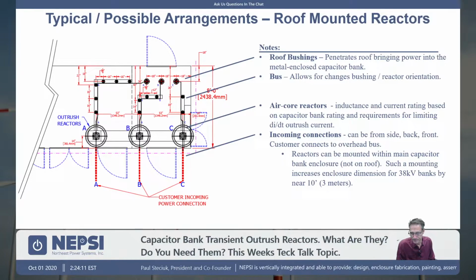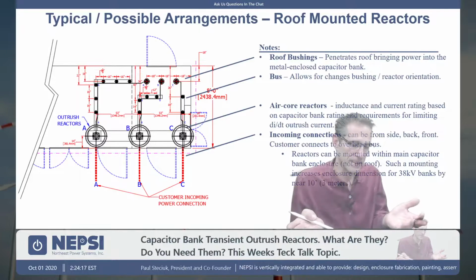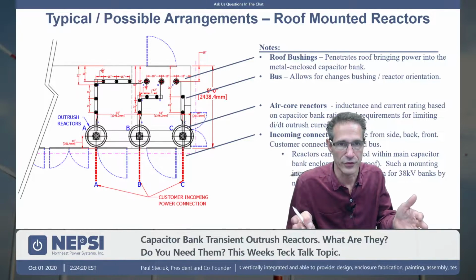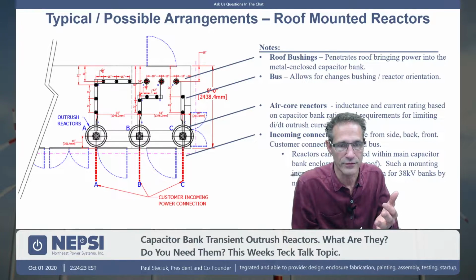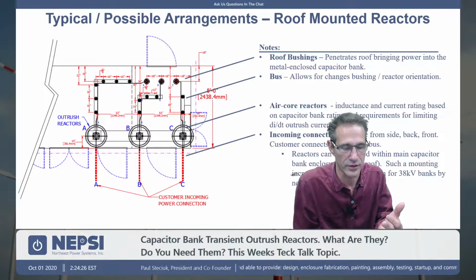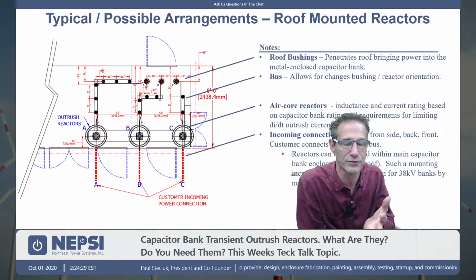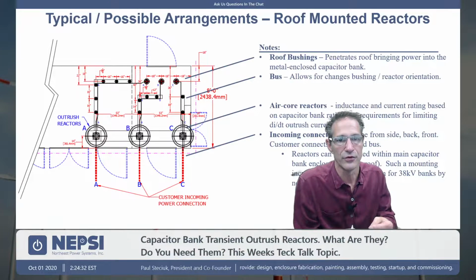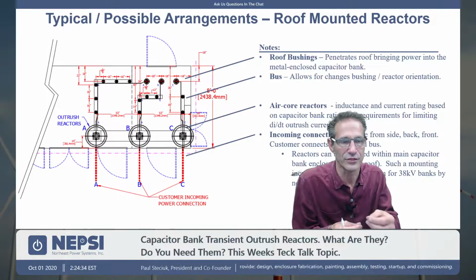We got a question. Yeah, Paul, we have a question from Christian. Are there cases in which increasing the inrush reactor inductance is more cost effective than installing additional outrush reactors? That's a good question. First of all, if you're in a renewables environment and you have capacitor banks, unless you're using some point on wave switching, like the VD4CS or some other type device, or you're using a Southern States cap switcher, which has a pre-insertion resistor technology, you're going to be required to put some type of transient inrush reactors in the bank.